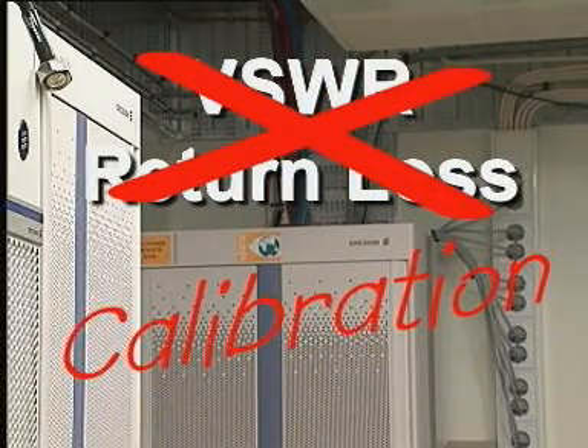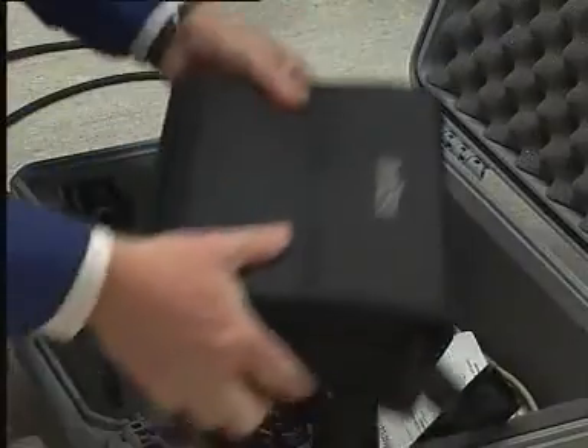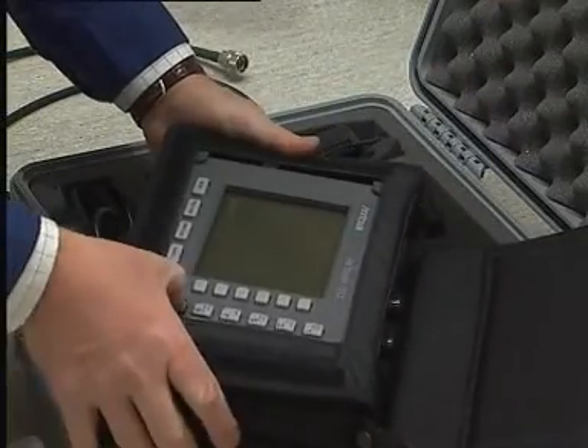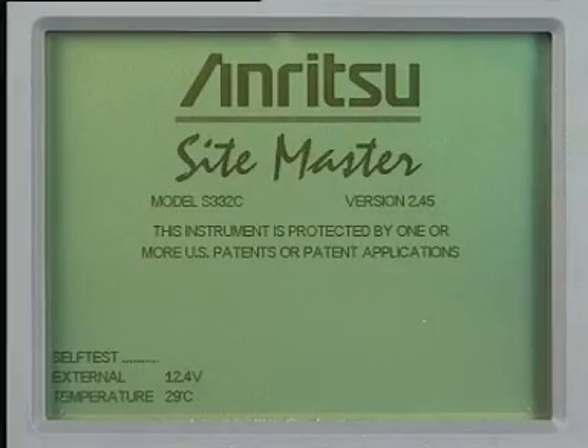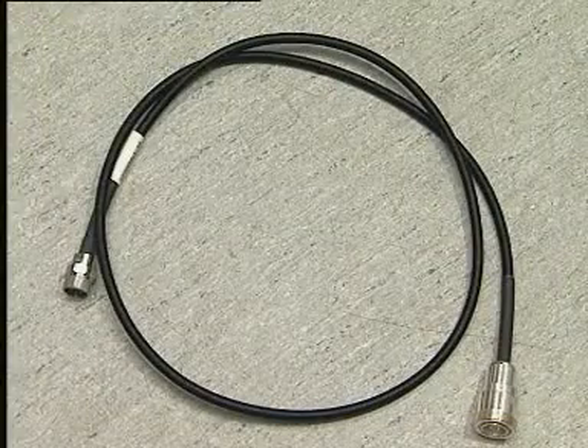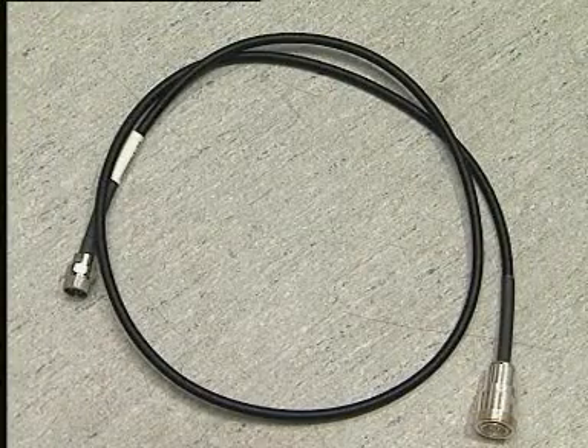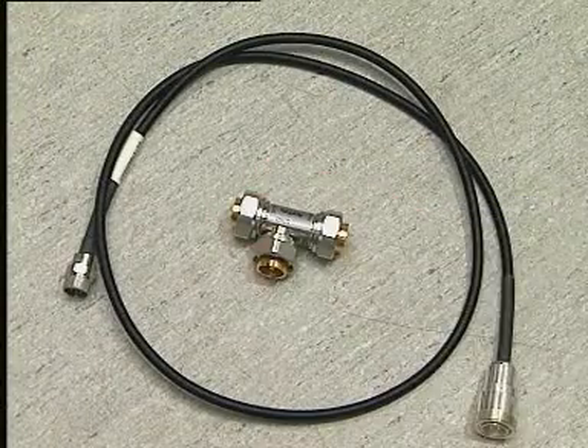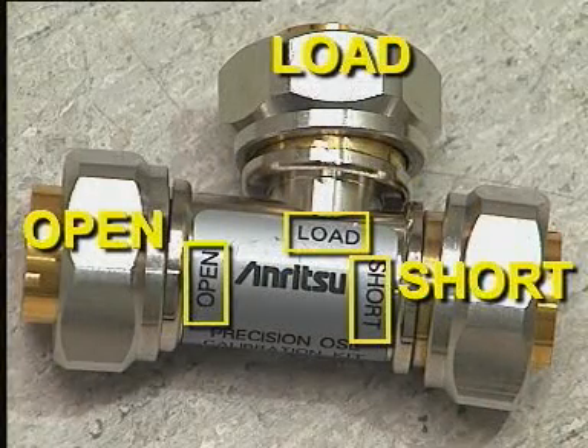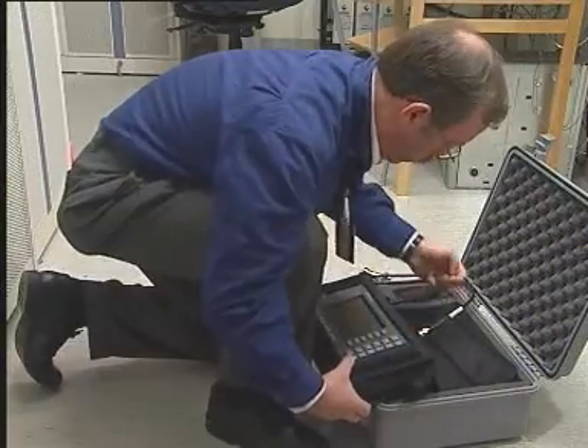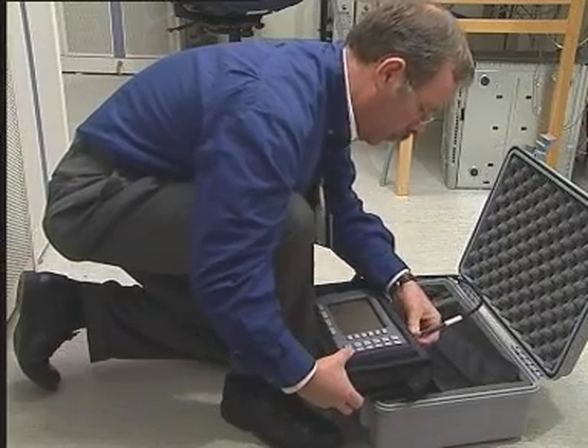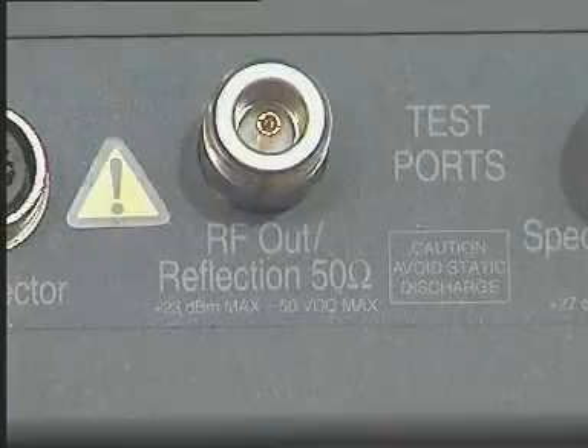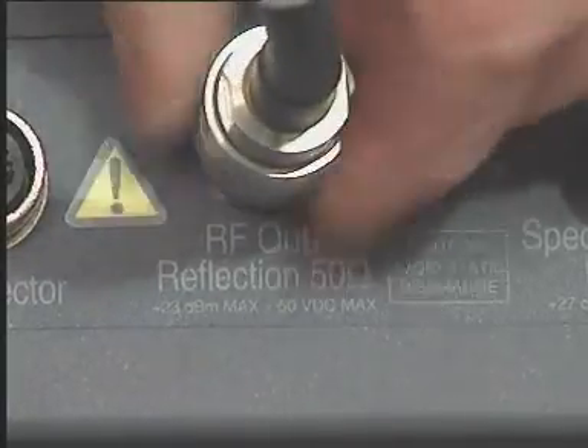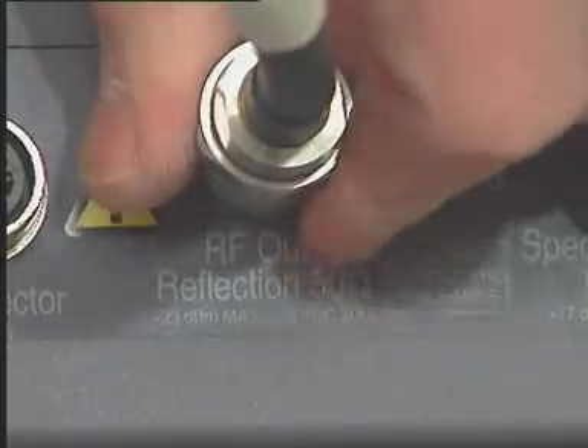Whenever the Sitemaster is first switched on, it must be left for a few minutes to warm up and stabilize. The Sitemaster package contains a phase-stable extension cable and a calibrated terminator. Connect the extension cable to the RF out reflection socket. The calibration will take into account the properties of the cable so accurate measurements can be made.